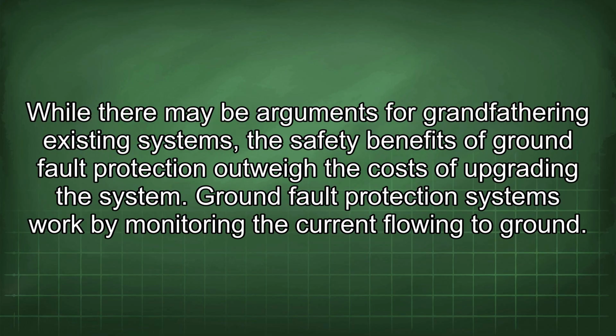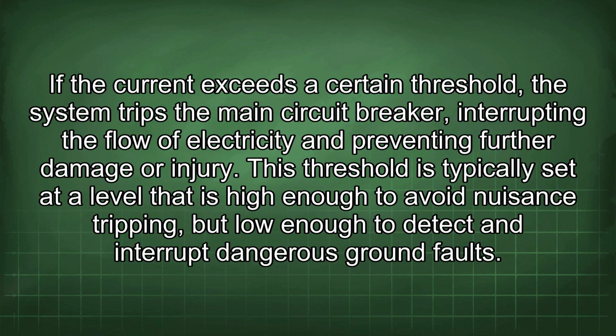While there may be arguments for grandfathering existing systems, the safety benefits of ground fault protection outweigh the costs of upgrading the system. Ground fault protection systems work by monitoring the current flowing to ground. If the current exceeds a certain threshold, the system trips the main circuit breaker, interrupting the flow of electricity and preventing further damage or injury. This threshold is typically set at a level that is high enough to avoid nuisance tripping, but low enough to detect and interrupt dangerous ground faults.